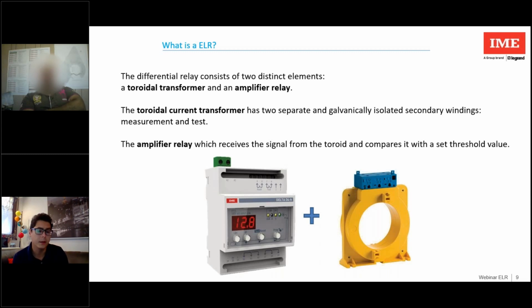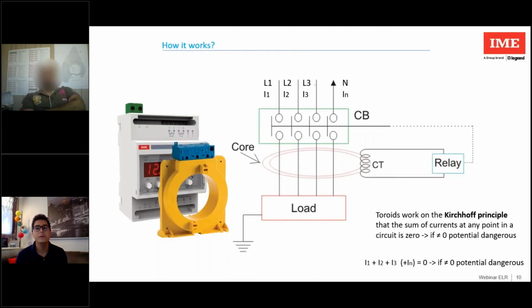How does it work? It's very simple. All cables or busbars pass inside the toroid. A current will flow in each cable or busbar. This current is represented as a vector. The toroid works on the Kirchhoff principle. The vector sum of the incoming currents must be 0. If it is different from 0, then we have a potential dispersion and therefore a potential danger.